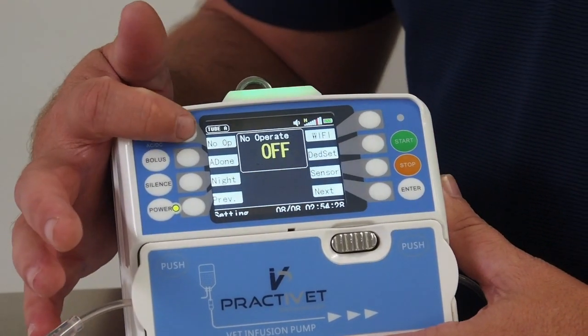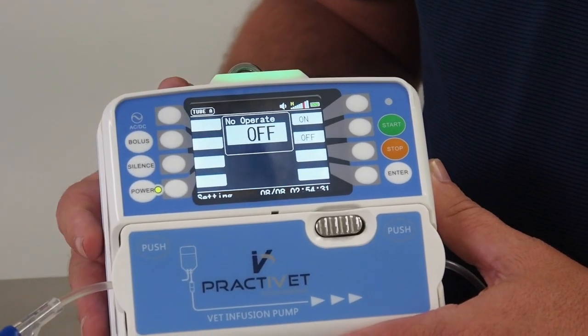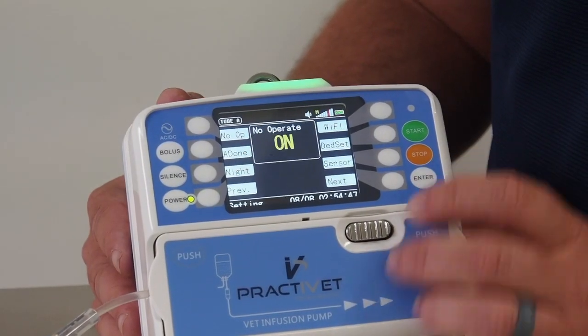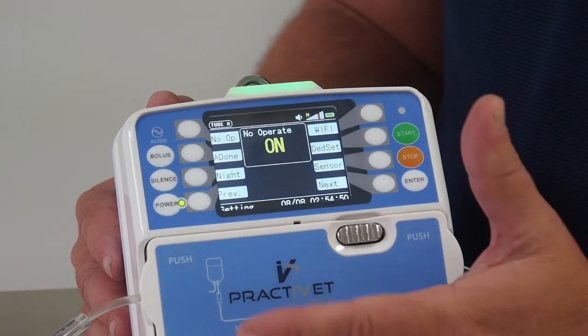I also like to recommend that users turn on the no operation to on. This will set a 1-minute timer once you finish programming the pump, and if you do not hit the start key, or you forget to hit the start key, in 1 minute the pump will alarm to remind you that it is not operating. The almost done soft key, I don't recommend that necessarily. That is going to give a 3-minute alarm 3 minutes before it's done pumping. Night mode will switch the backlight to low and turn the sounds down to low within 1 minute after hitting the start key.